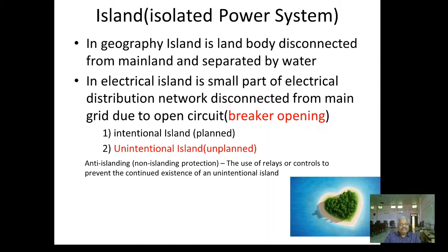Here you can see islanded operation of distributed generation with utility load is generally not allowed. Here you can see this is the utility substation. Here one distribution feeder is going, second is going, third is going, and on the third you have distributed generation supplying its load. Now when this circuit breaker opens, what happens? This dotted part becomes an island, and this distributed generation supplies this load as well as all the load on the distribution system.